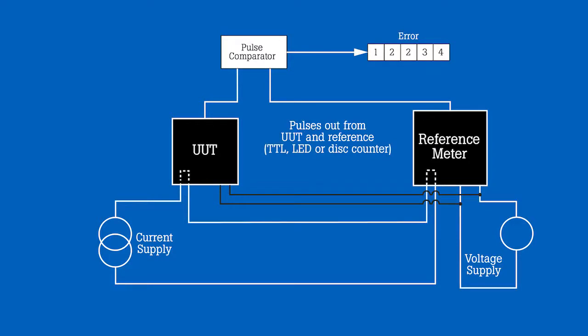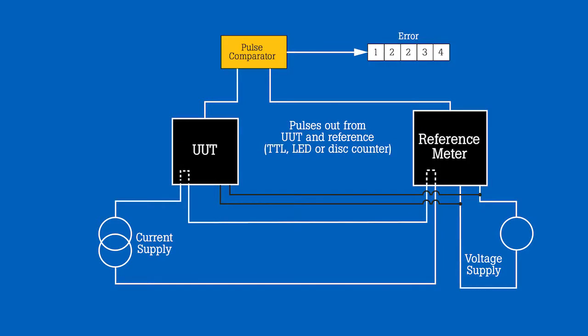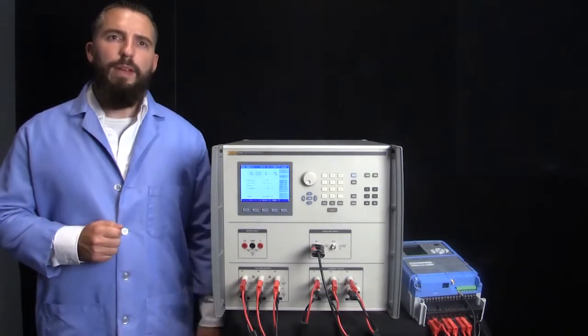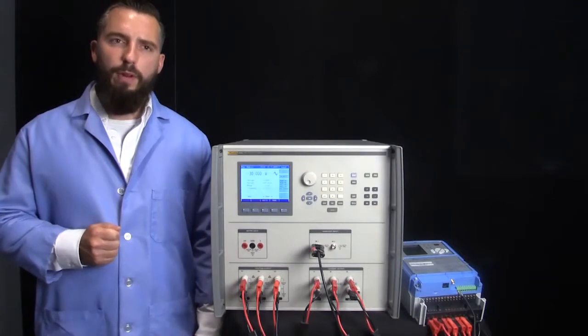Three separate pieces of calibration equipment are required to complete this task. One, a power supply that can provide three phases of voltage and current. Two, a three-phase reference energy meter. And three, a device for counting pulses both from the reference meter and the UUT, which then compares the two counts. As you can imagine, this is a lot of work to make sure that each piece of equipment is connected and communicating properly.